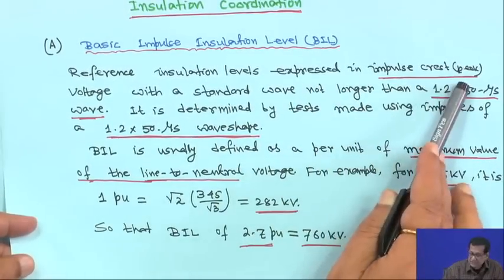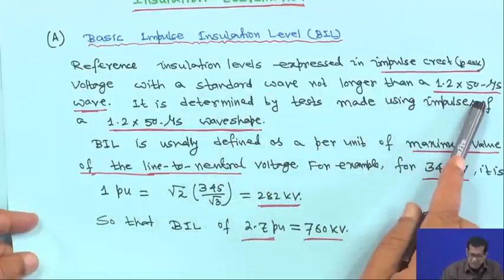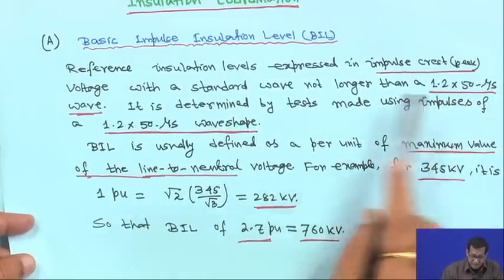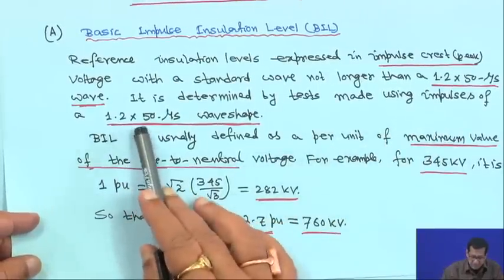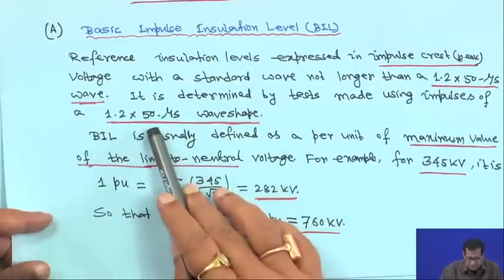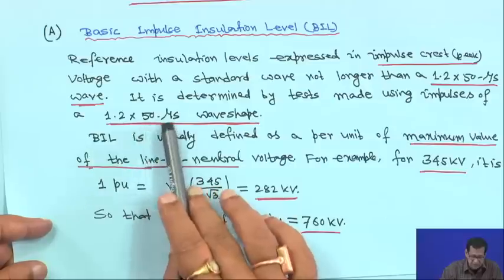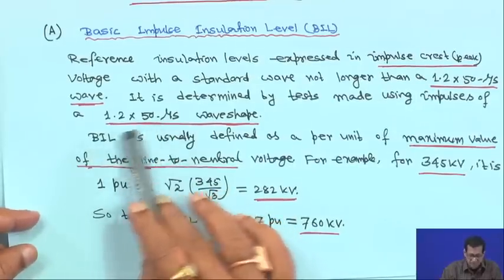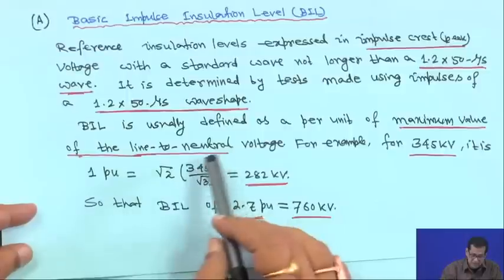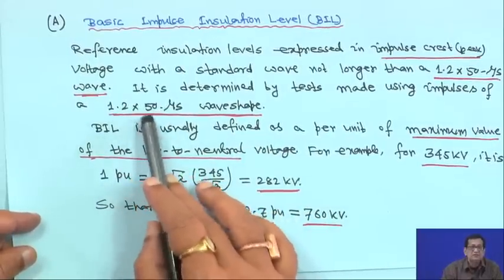The insulation level is expressed as the peak value with a standard 1.2×50 microsecond wave, where the peak is reached in 1.2 microseconds and 50 percent of that value is reached at 50 microseconds. It is determined by tests using impulses of 1.2×50 microsecond waves, though in practice the values may not be exactly these but close to them.